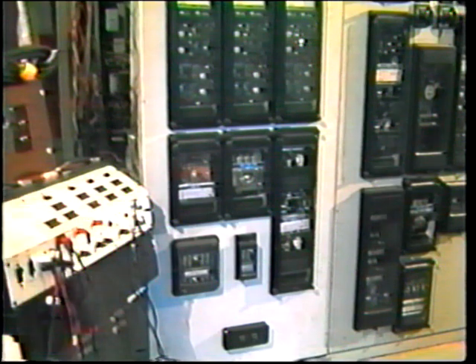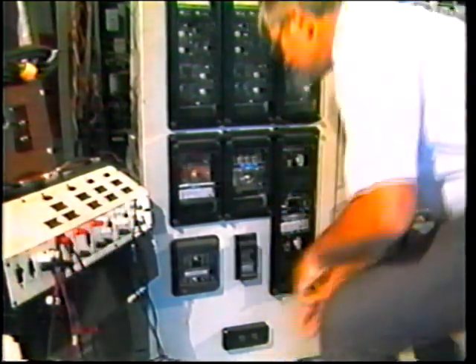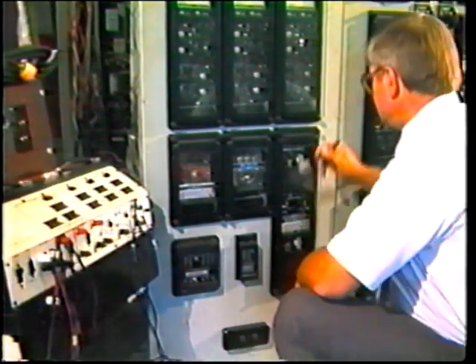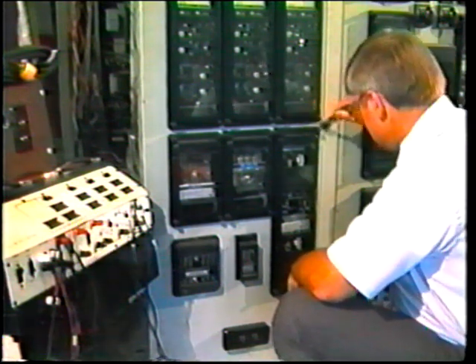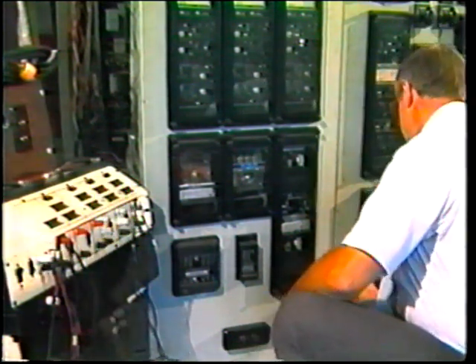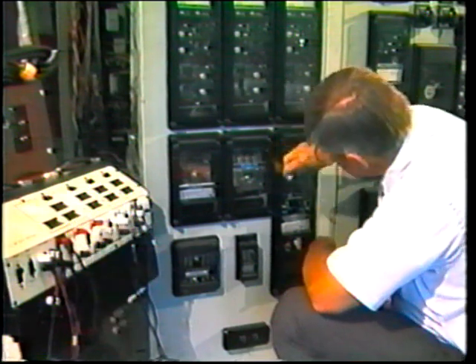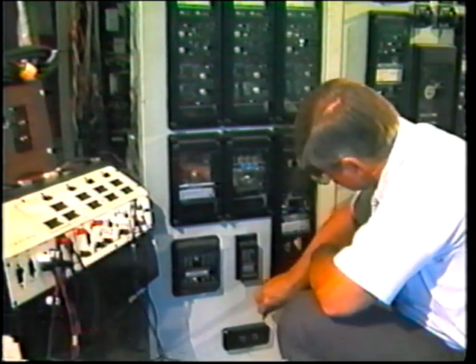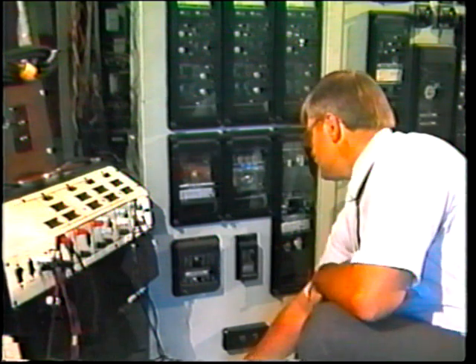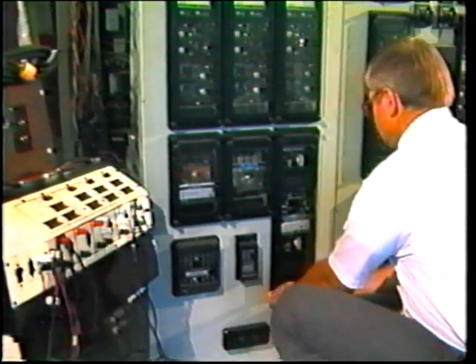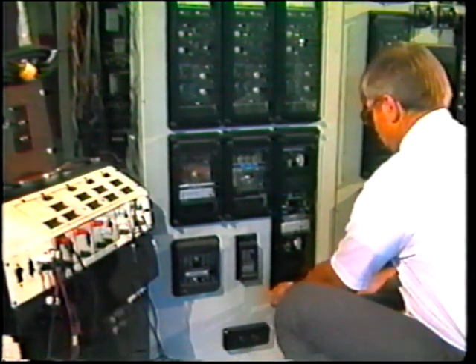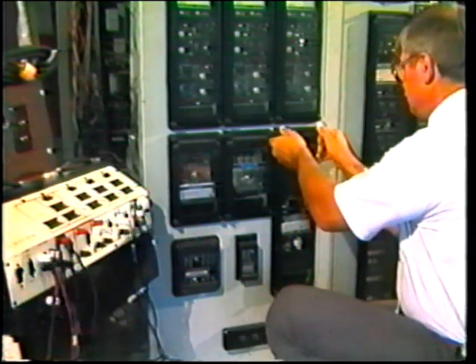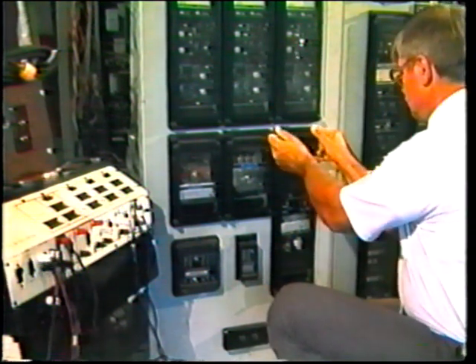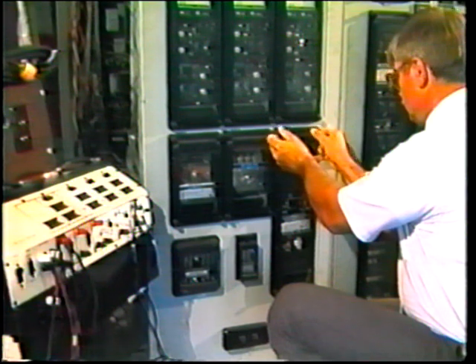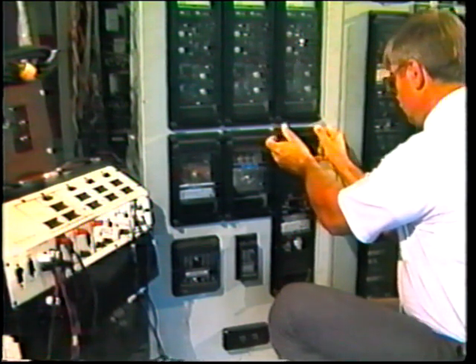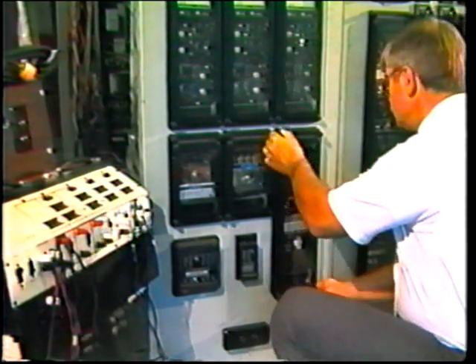Now, here is another example, and this is actually quite a common problem. This technician was working on live equipment to perform in-service tests. He was removing the cover of the directional overcurrent relay, which is located right at the bottom of the panel. The technician had to squat to remove the relay cover. While doing this, the target reset lever on the cover became misaligned, allowing it to mechanically lift the target seal-in contacts, causing the trip circuit to operate.